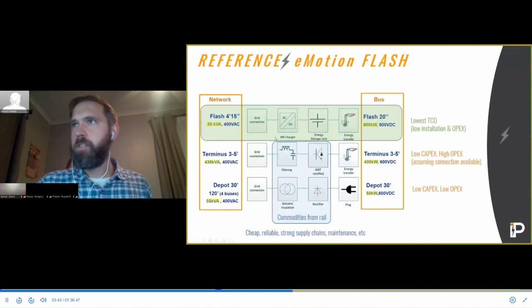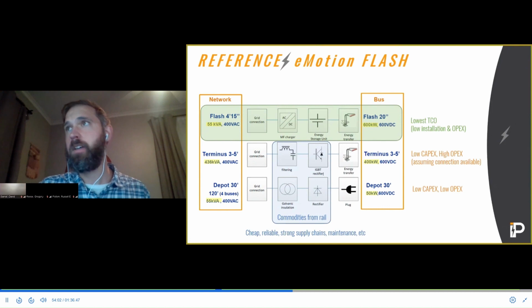They've got a few different infrastructure options. With a 20-second 600 kilowatt flash charge, that's a very high peak demand, but another bus might not arrive for another 5 or 10 minutes. You wouldn't want to draw that directly from the grid, or your peak demand charges would be through the roof.